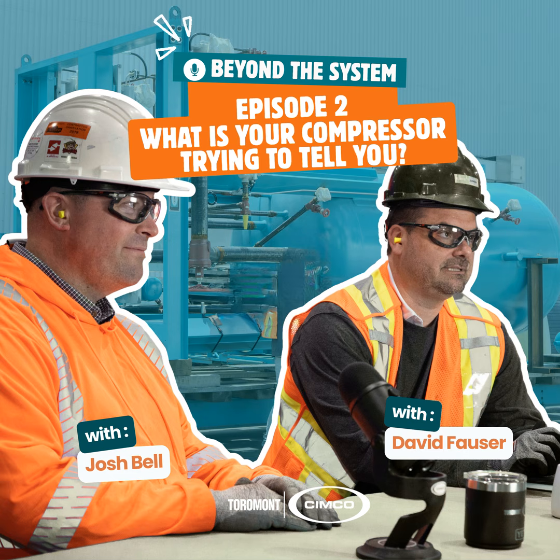This one can be really tricky because I talked to some of our really senior mechanics here, and their philosophy is that as long as the compressor is maintained, you could just keep going forever with some of the recips, etc. But let's talk a little bit about replacement, because it's not as linear as it is with other components in the system, because of their maintainability, especially for open drive type compressors.